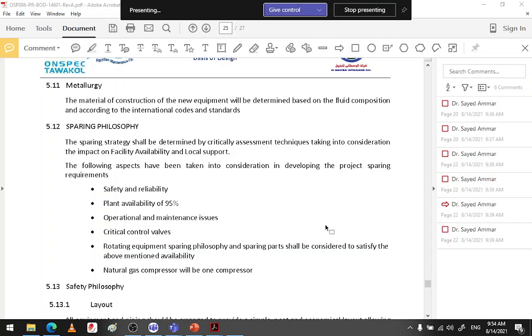Good. How does this impact your design? One aspect is the sparing philosophy. What does this mean, Raja? This means if we're going to construct a plant having one pump, if this pump fails, the plant will shut down. Based on the availability of the plant signed in the contract, we added a standby pump to make sure that the failure of the pump will not affect the plant performance. If one pump fails, we have the other one standby to kick in.